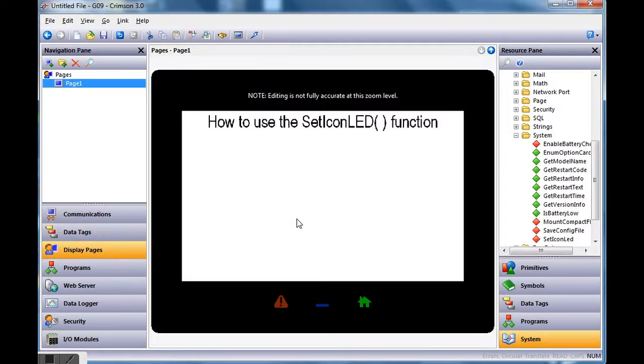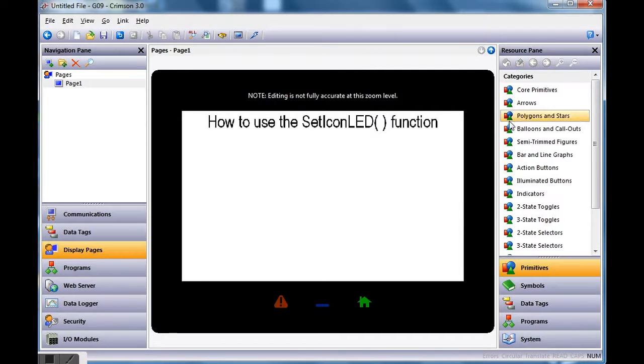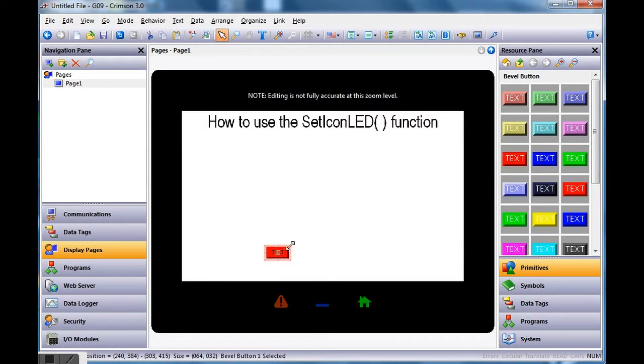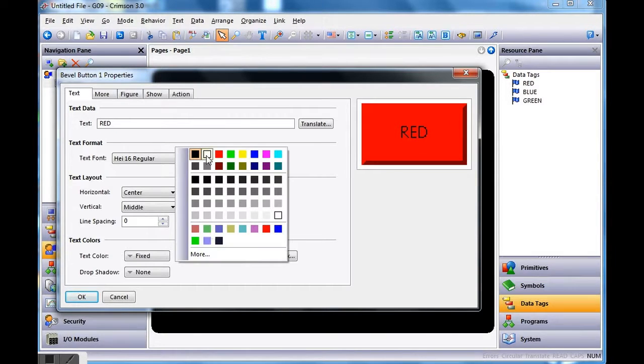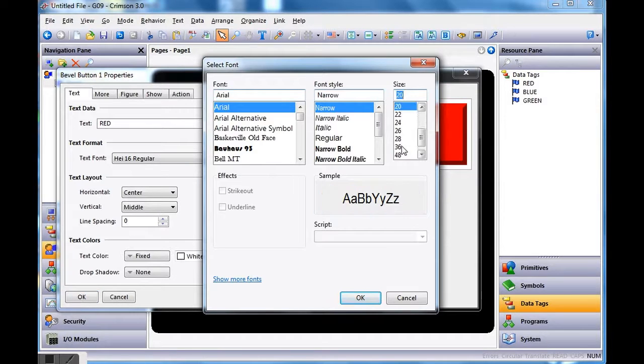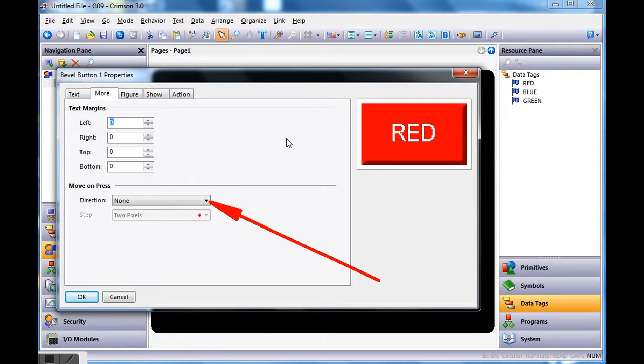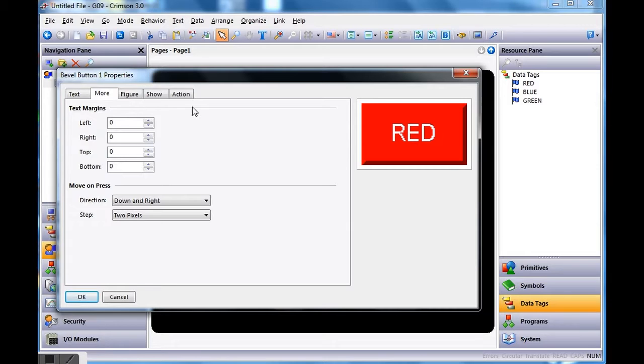Now I'll go to Display Pages and put these buttons on screen. I'll go to Primitives — Core Primitives at the top — scroll down to Bevel Button and drag the red one out, make it a little bigger, and place it. I'll right-click, go to Properties, and on the Text tab change the wording to 'red' and make the font white so it contrasts better. On the More tab, I like to hit the pull-down and choose Down to the Right for a 3D movement effect.